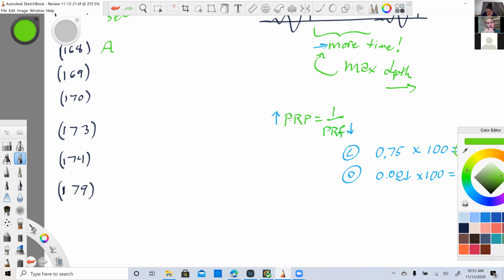Remember, we can't change frequency. Same transducer, same machine. I know, yes, we can technically, but according to Element, we can't change the frequency. So remember that. Pulse duration. Pulse duration is decided right there in the transducer. That backing material keeps that transducer element from ringing. That's what causes the pulse duration.